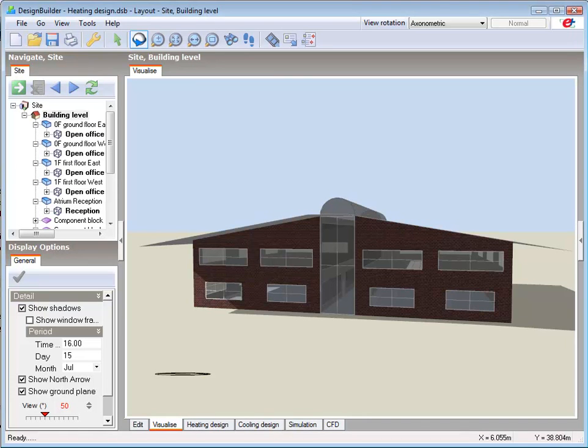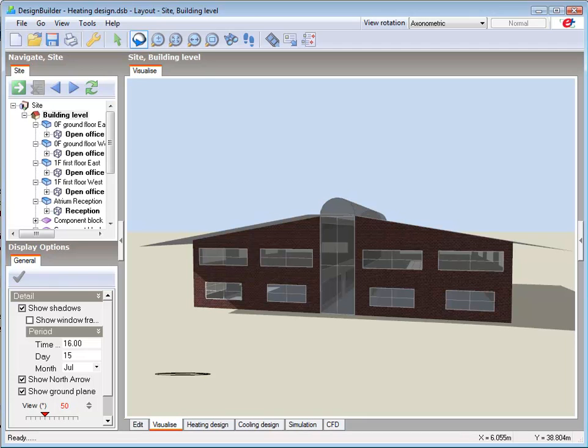Heating design calculations in DesignBuilder use a constant steady state external temperature set to the winter design external temperature, which is taken from the weather data set relative to the location of the building. The wind speed and direction are set to design values and there is no solar gain. No account is taken of internal gains such as lighting, equipment and occupancy.